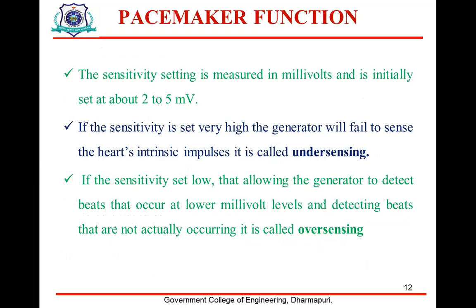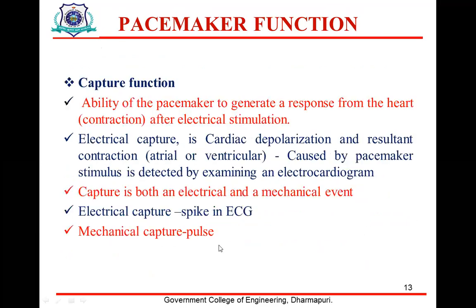Another function of the pacemaker is sensitivity, which is measured in millivolts. Initially, it is set between 2 to 5 millivolts. If the sensitivity is set very high, the generator will fail to sense the heart's intrinsic impulse. This is called undersensing. If the sensitivity is set low, the generator can detect beats that occur at a lower millivolt level, and it may detect beats that are not actually occurring. This is called oversensing.